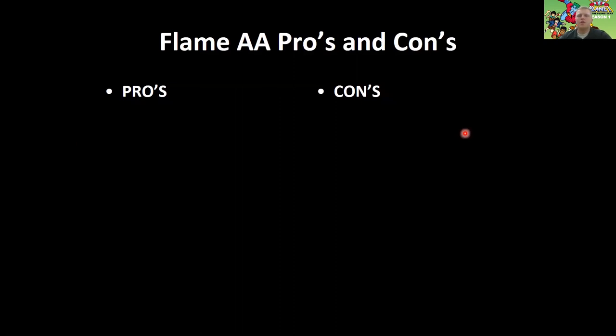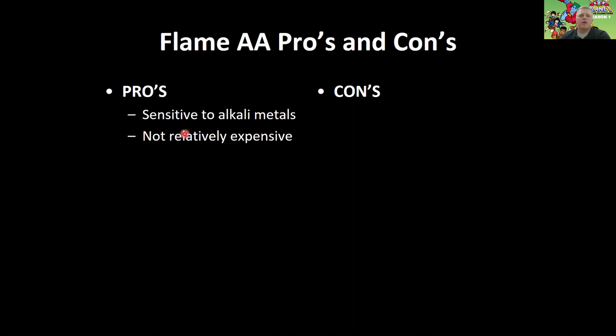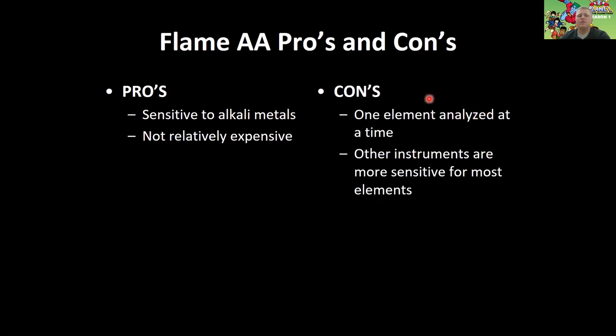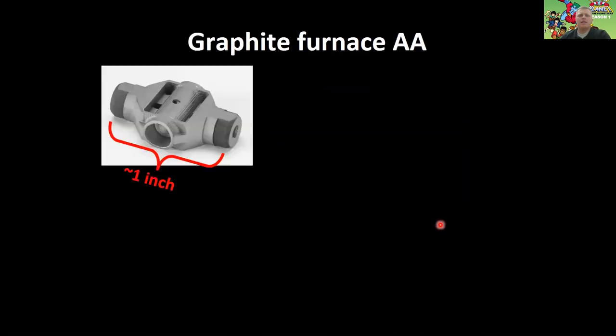Flame atomic absorption has some pros and cons. Pros: it's really sensitive to alkali metals — you can measure at parts per billion or parts per trillion if you're careful — and it's also relatively cheap compared to other techniques. Cons: since you're using a hollow cathode lamp, you can only analyze one element at a time, which is a big drawback, and other instruments are more sensitive for most other elements.